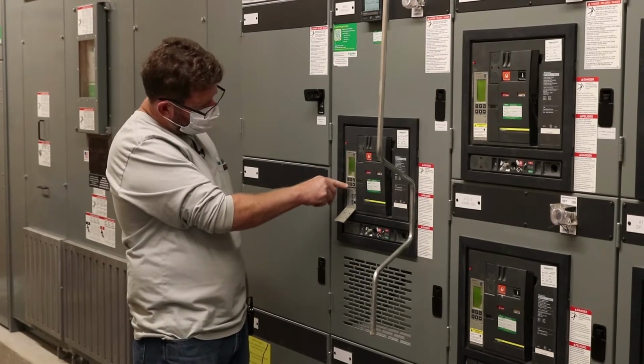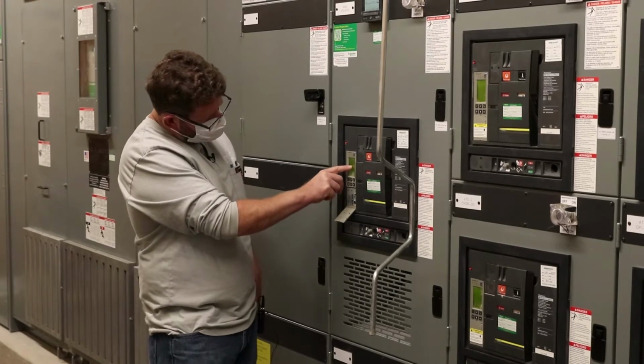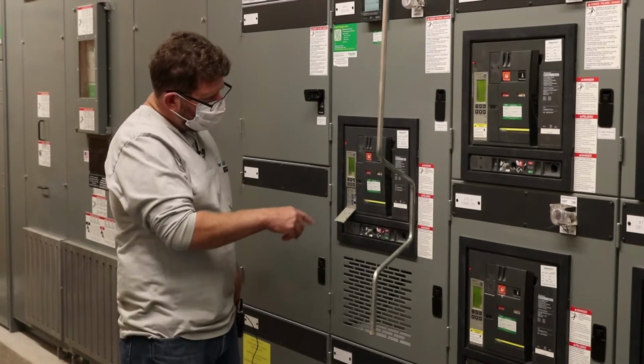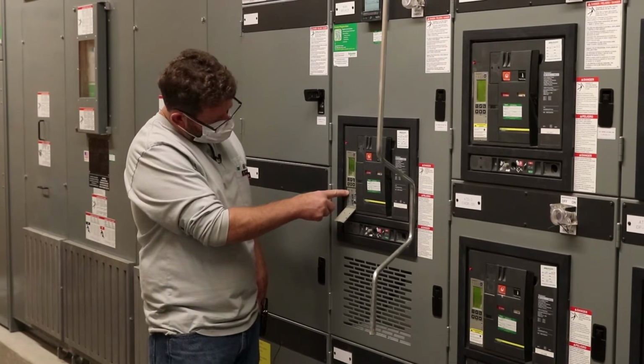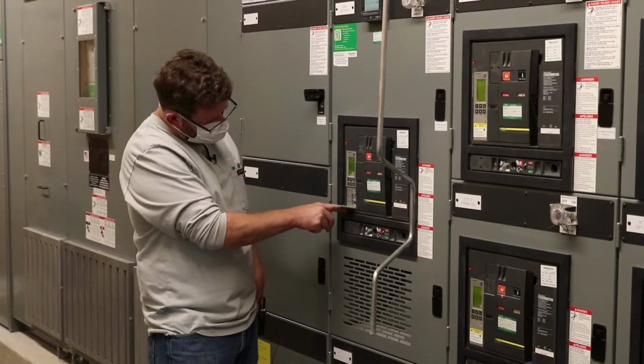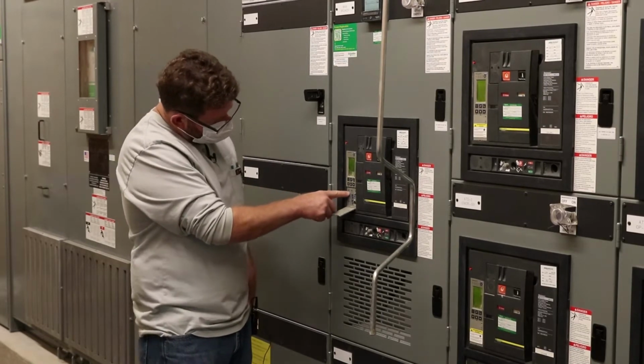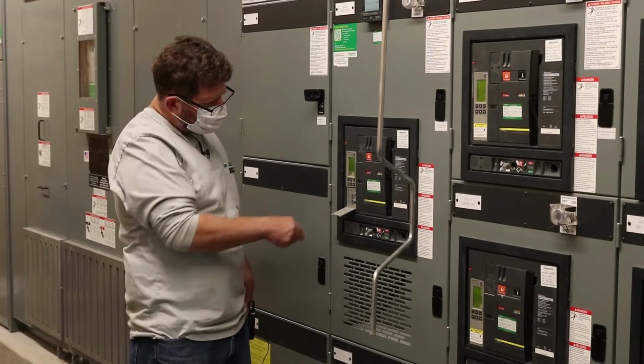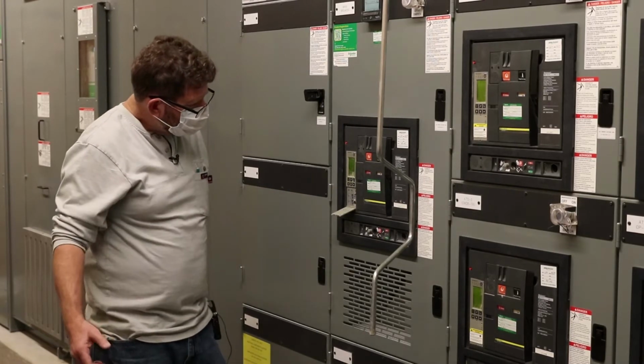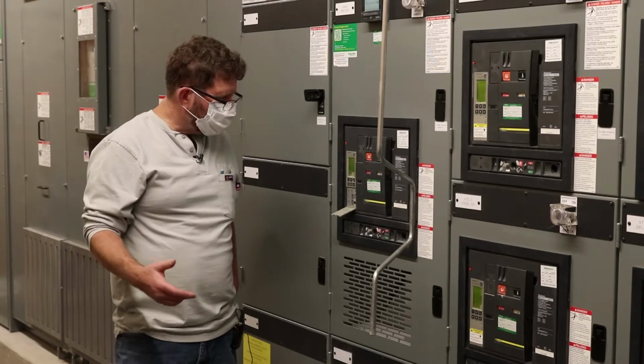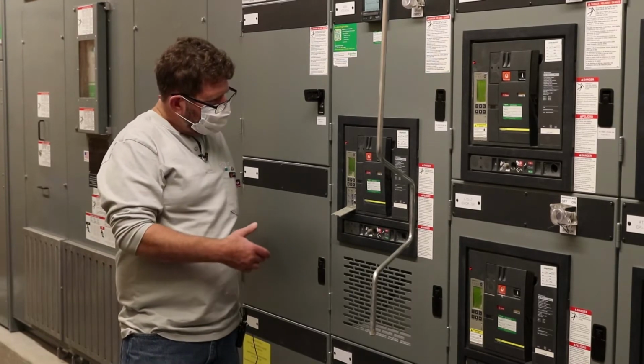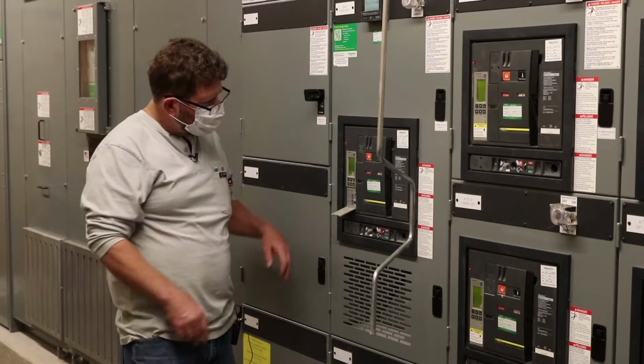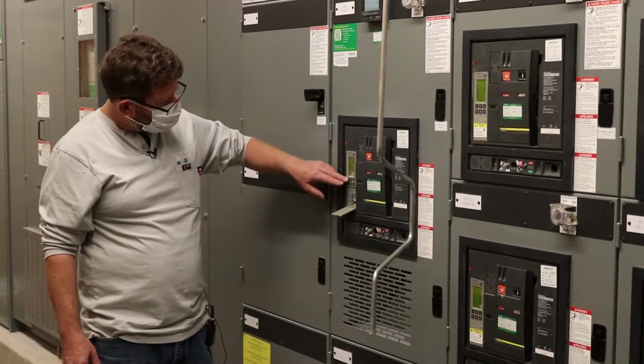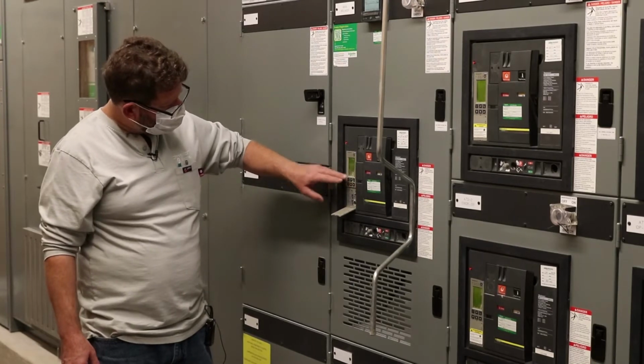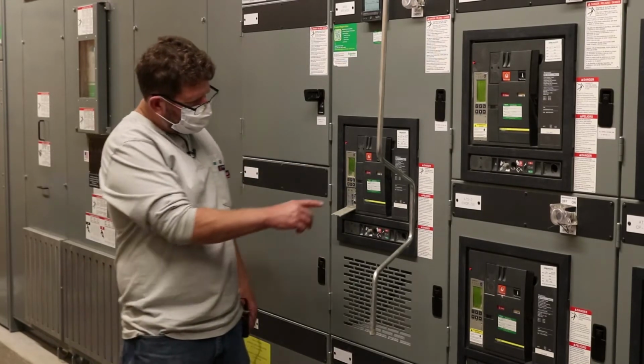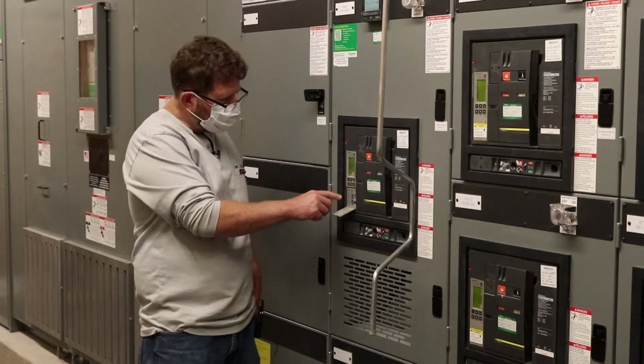We're showing current protection. Right now your long time setting is 3200, and that's determined by this dial here. 1.0 times 3200 is your setting. The next value down is 0.9. So if you were supposed to set a setting somewhere between 0.9 of 3200 and 3200, you could dial it to 1, and then you could scroll down to the 3200, select it, and then you could fine-tune it with these keys here.